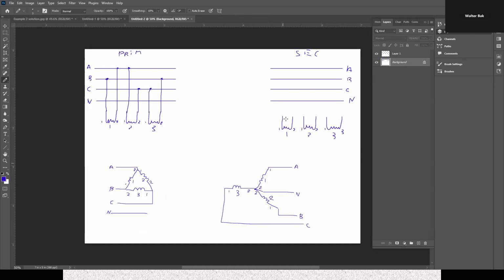Coil 1 goes to A, terminal 1 goes to A, coil 1 terminal 2 goes to neutral. Notice that in delta, neutral is not connected.